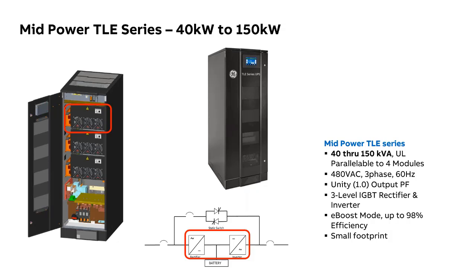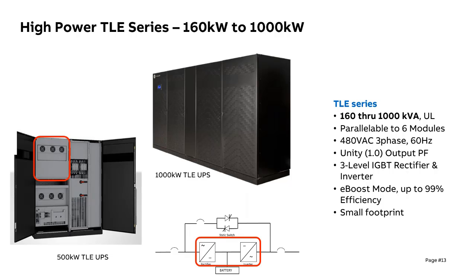That's true for not only ABB, but for all vendors in the industry. It's not meant to be a scalable product. So just for illustration, it's very parallel to the next two slides. I'm just going very quick. The high power ones are the same thing, for the ABB UPS high power. This product box is now just based on a 250 kW module. So the one at the bottom here, we can see there are two modules. It's rectifier and inverter, 250 kW, one frame that has space for two of them, and the one in the middle of the slide here with all the doors closed actually has four of them built in, but they're bolted in, and they just are hard in parallel, offering, like in the big one, 1 megawatt of power.